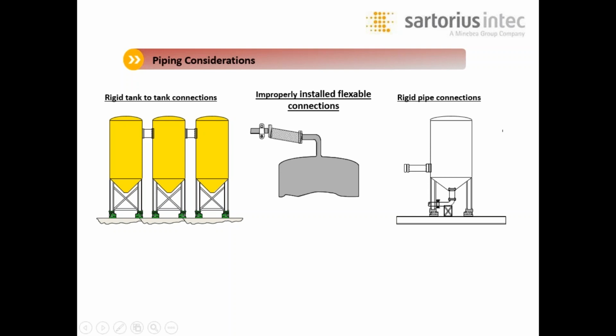Most importantly, and most times overlooked, is the piping considerations when talking about a tank and silo system. Anything that is installed on the tank that prevents the free motion of the vessel will reduce the accuracy of the system. Rigid tank-to-tank interactions will cause fluctuations from one tank to another. Any piping should also be fixed with the same support as the structure shown above. The rigid piping you see on the tank on the right needs to be replaced with flexible piping. The flexible piping you see in the center is basically rigid piping because all the flex has been taken out of it in the installation. And rigid tank-to-tank connections can cause a problem as one tank may drag down the other two.